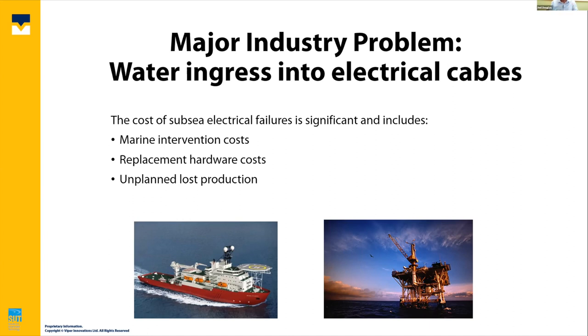But when you do get an insulation resistance failure, it ultimately leads to marine intervention costs, replacement of hardware costs, and, as I've indicated, unplanned loss of production. Most clients, and when I talk about clients, I'm talking about operators here, will work on the basis of when, not if, they have an insulation resistance failure or water ingress into their system. So most of them will plan for it and not just close their eyes, keep their system turned on and ignore this key measure of IR, or insulation resistance.